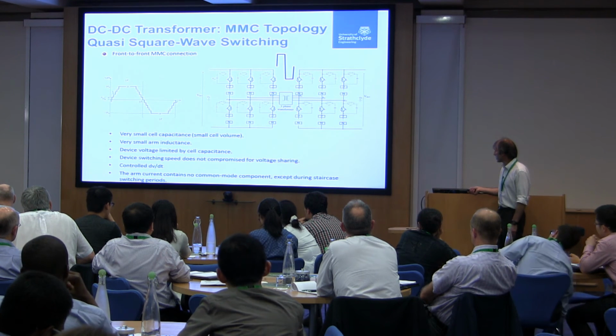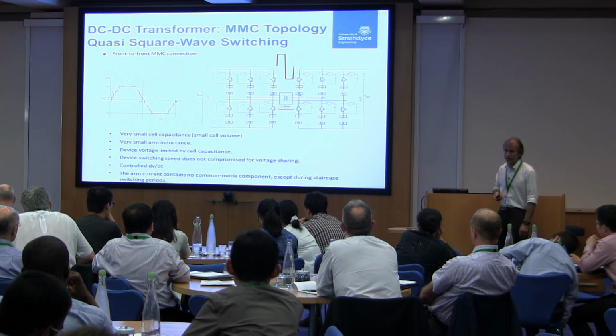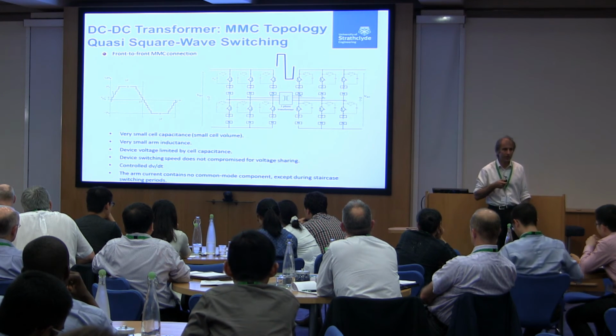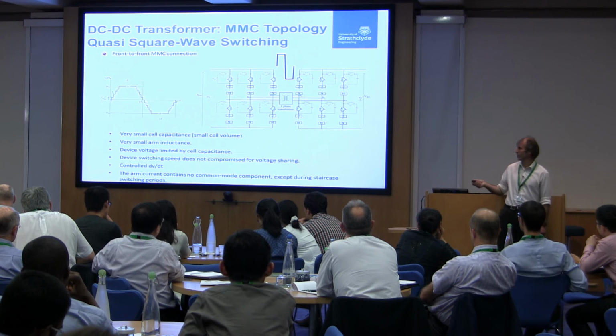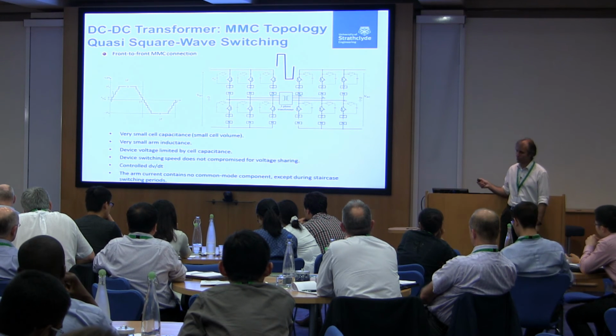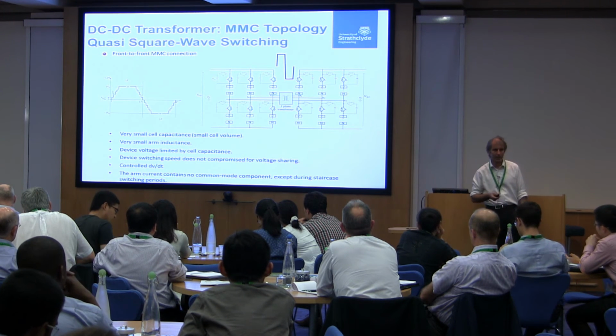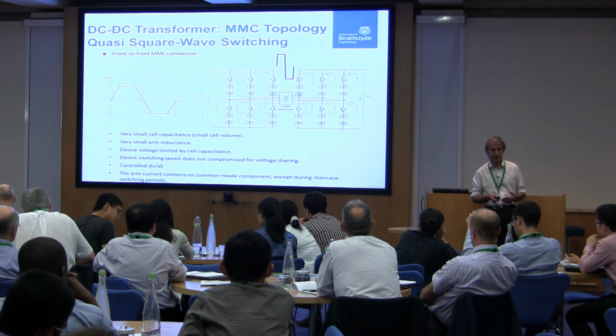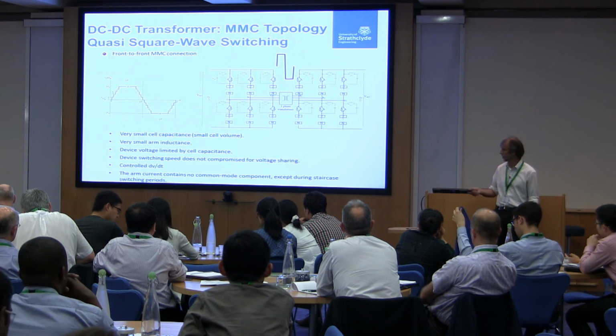The arm currents with this design, unlike the MMC, don't contain a continuous DC component to top up the capacitors. Because we're operating those cells effectively as a snubber, you only see the energy being transferred in and out during the switching transition on that slope.